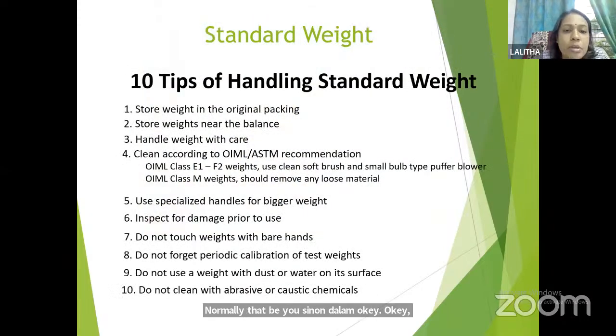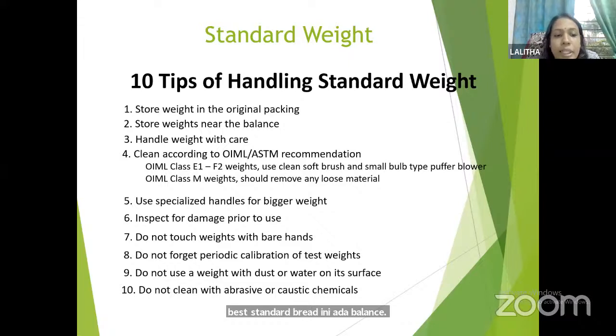Standard weight, 10 tips for handling the standard weight. First, store the weight in the original packing. The weight always has to be in the original packing. We cannot take anything out of the original packing. Always store the standard weight near the balance. Handle the weight with care. Then clean according to the standard recommendation. If you're using OIML class E1 to F2, they have their own recommendation as well.